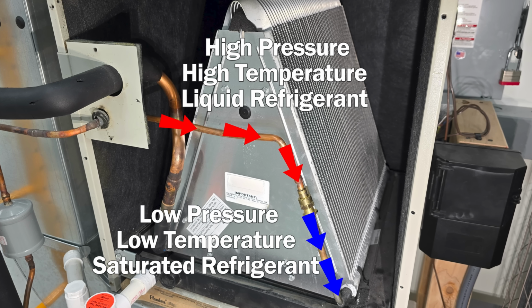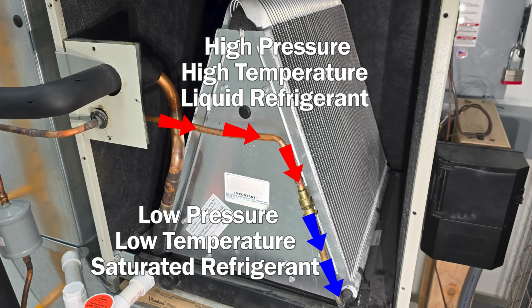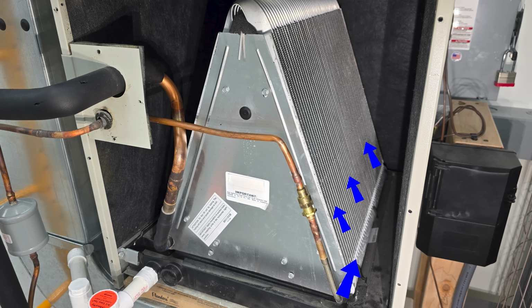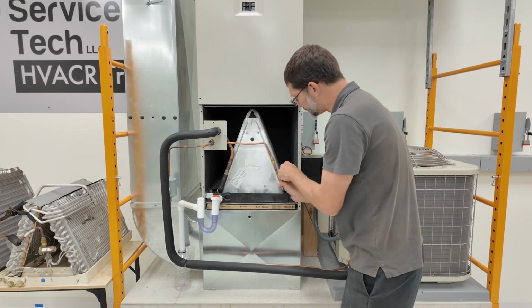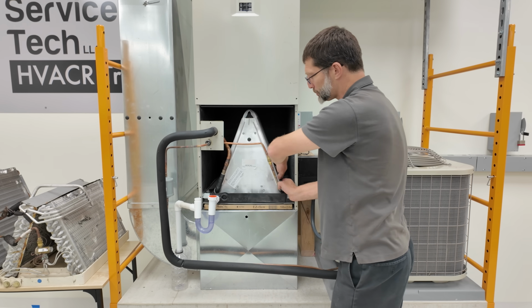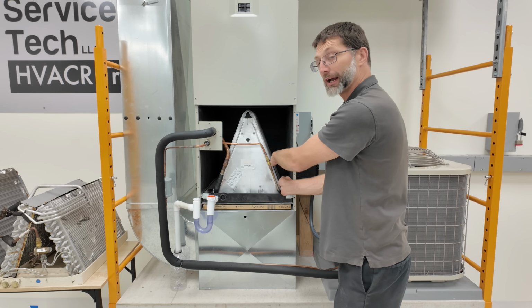You'd have high pressure, high temperature liquid refrigerant entering the metering device, and you'd have saturated refrigerant exiting the metering device. It's going to be low in pressure and low in temperature. Then it's going to come into the header, go into the microchannel coils, and go all the way through each one of these, traveling upwards.